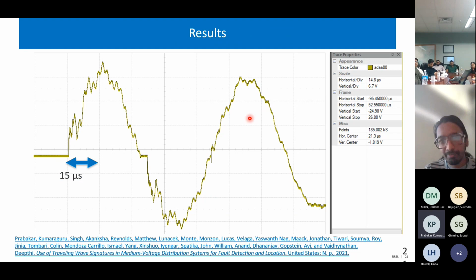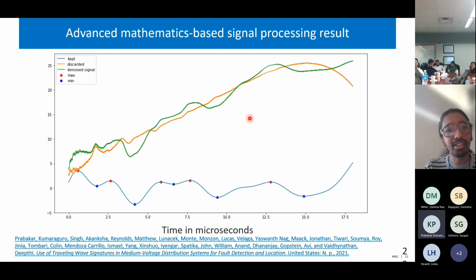We looked at the results. This is from the scope capture, and one half cycle is almost 15 microseconds, so you have to filter this out. We used some novel techniques to extract the traveling wave from the raw waveform, basically a kind of subtraction. The orange is the discarded waveform, and green is the denoised signal from the scope. We discarded the orange based on the speed of light and the frequency, essentially doing a high pass filter that tells the signal processing to ignore everything low frequency and only consider what is high frequency, which you can then justify as the traveling wave.